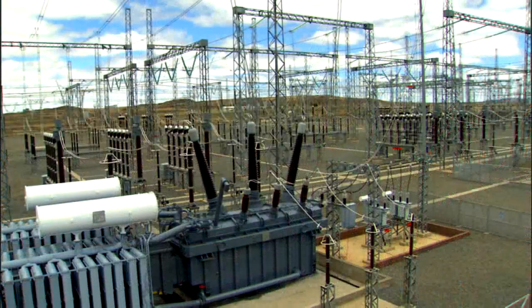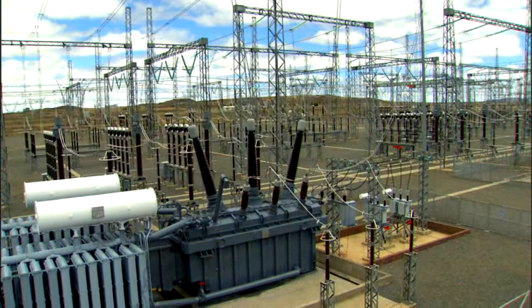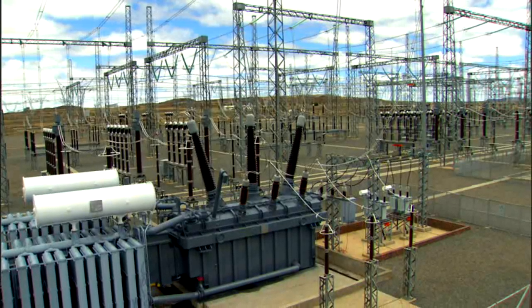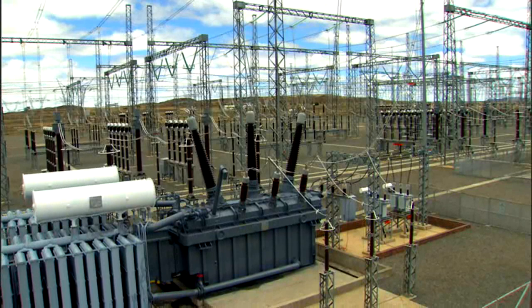For transformers, the power factor or the dissipation factor shows aging, water content of the oil and paper, and contamination with conductive particles.